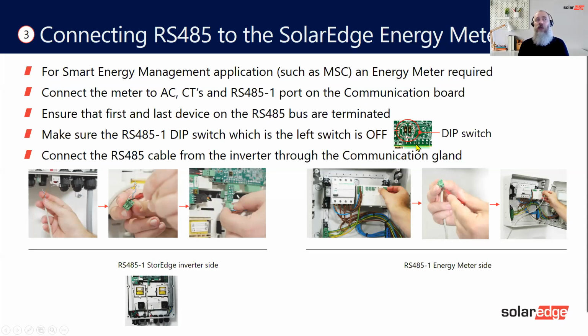You don't need a huge cable size for this, because there's only 7 volts traveling on this cable. The most you would probably need is a standard RS485 cable, a standard Cat5, Cat6, and you only need 1 pair. You don't need to double up, so just 1 pair. So 1 pair, either blue and white with blue, or brown and white with brown. That's a pair. Once you've done the connections on here, we'll look at these later on anyway. So a connection on the inverter, and then a connection on the meter, which is just here. That's that side done.